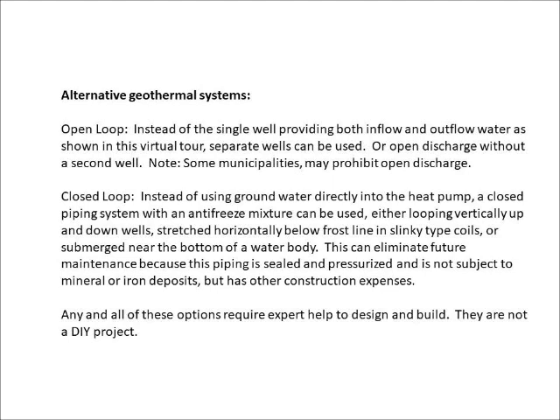Regarding closed loop systems, instead of using groundwater directly into the heat pump, a closed piping system with an antifreeze mixture can be used, either looping vertically up and down wells or stretched horizontally below frost line in slinky type coils, or submerged near the bottom of a water body. This can eliminate future maintenance because this piping is sealed and pressurized. It is not subject to mineral or iron deposits, but has other construction expenses.